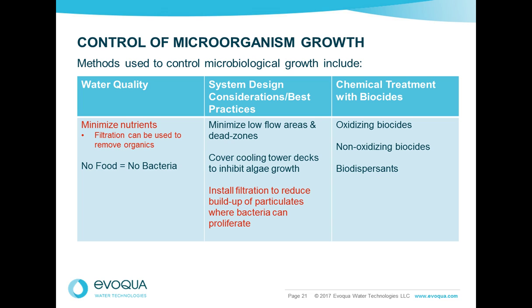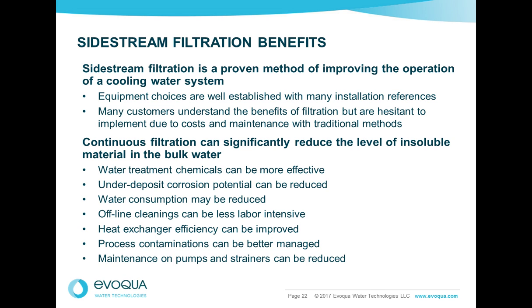Controlling microbial growth. I'm a big believer in oxidizing biocide. Keeping the water clean coming into the system is the first thing, and clean water generally has less food than dirty water. Dirty water is loaded with food and other microbiological growth, and growth begets growth. System design considerations often can aggravate the system. Minimize low flow areas. You want to keep the water moving. If the water is moving fast in the heat exchangers, the probability of forming a film on there is reduced. Oxidizing biocide, non-oxidizing biocide, biodispersant, it all helps. But again, chlorine is a key ingredient.